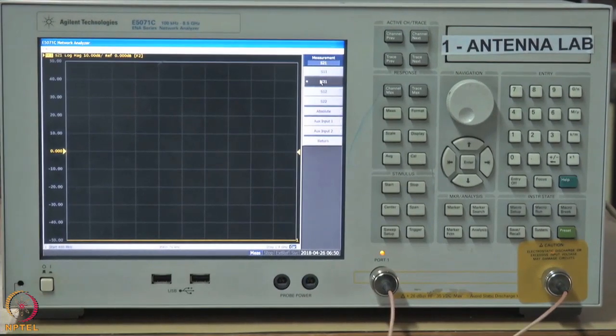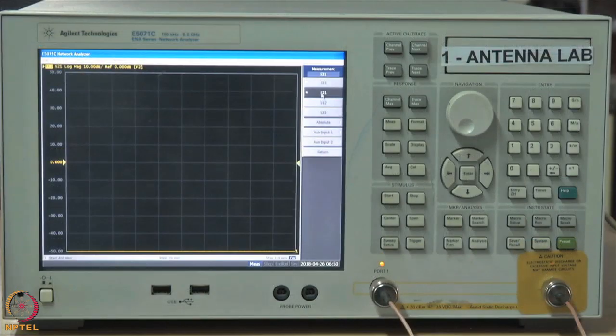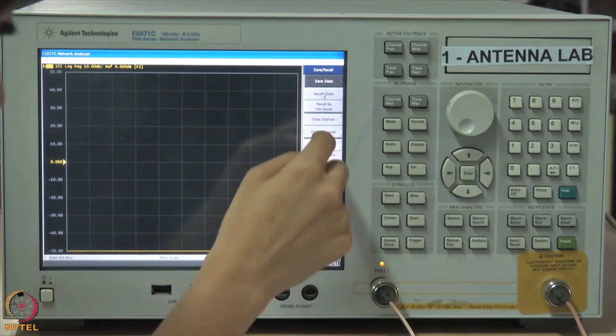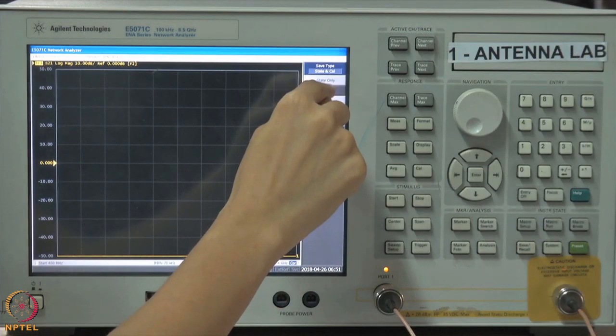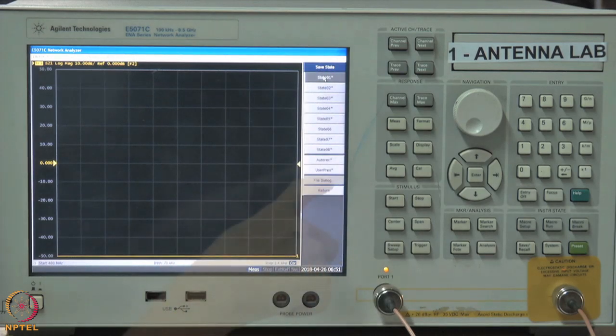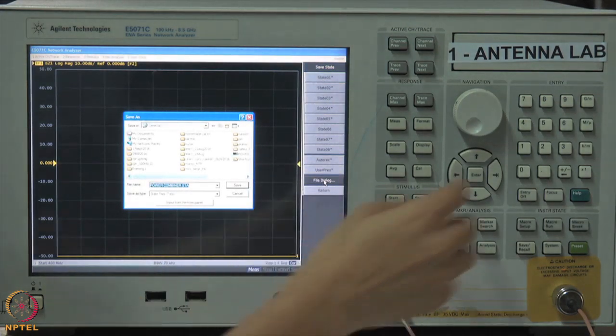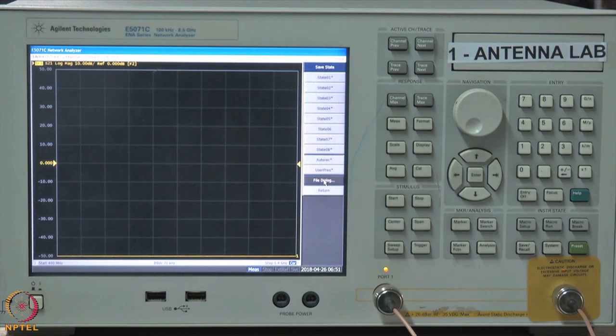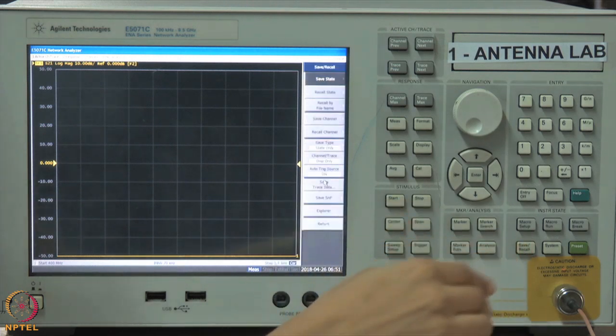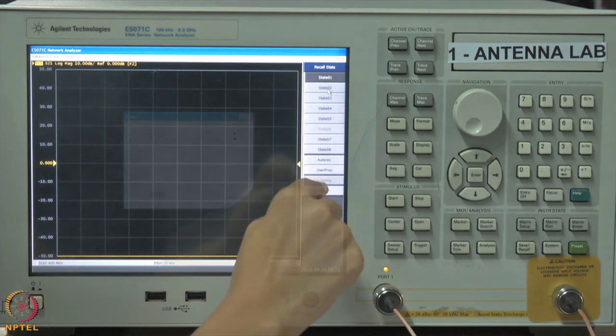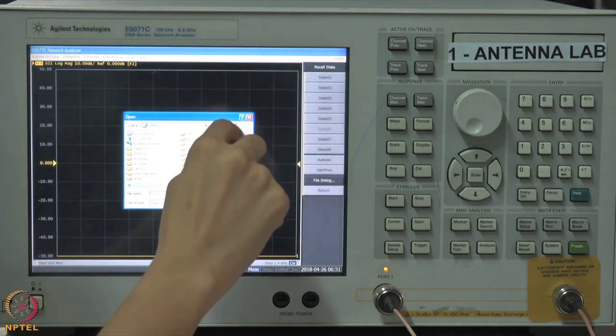Now connect your device to the cables to do the measurement. You can save the calibration state using the save/recall option: select save type as state and cal, then state only, and save with a name of your choice. At a later stage, if you do not want to repeat calibration, recall this saved calibration state using save and recall, then recall state, and select the saved file.